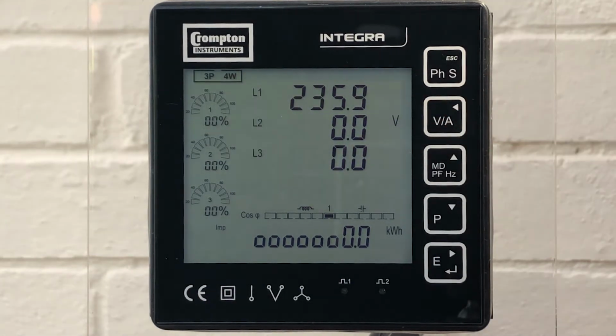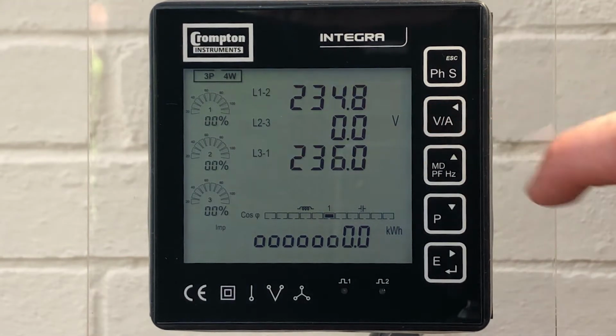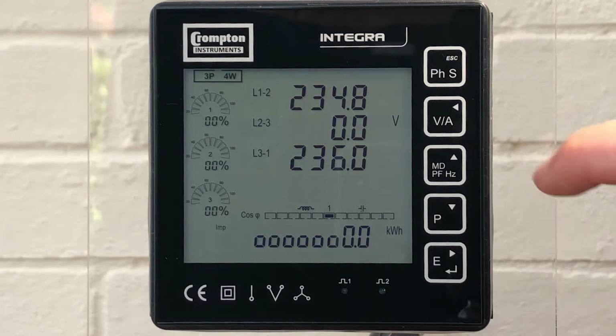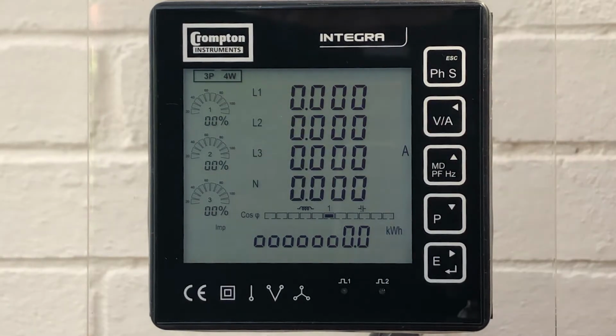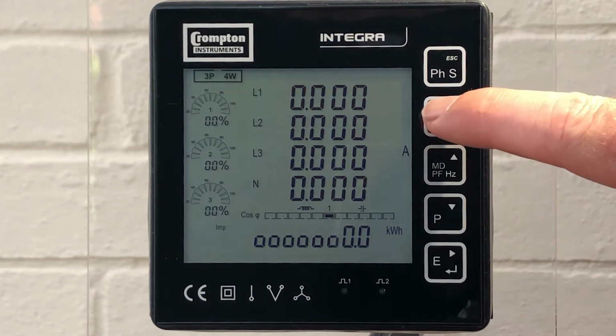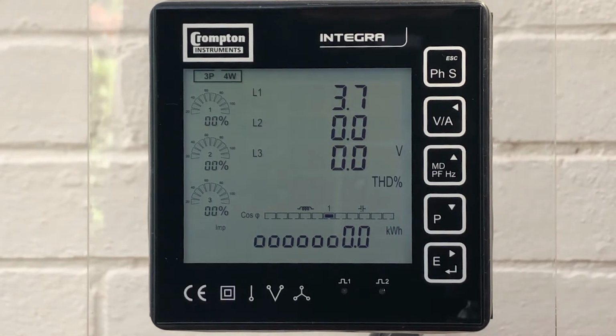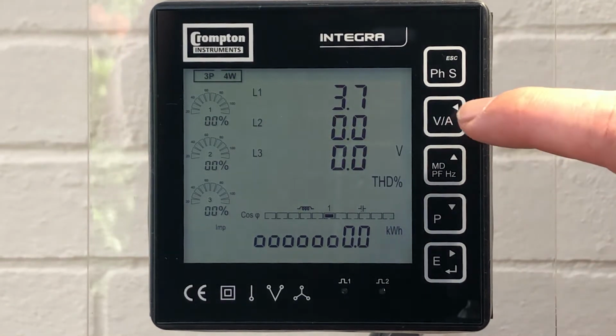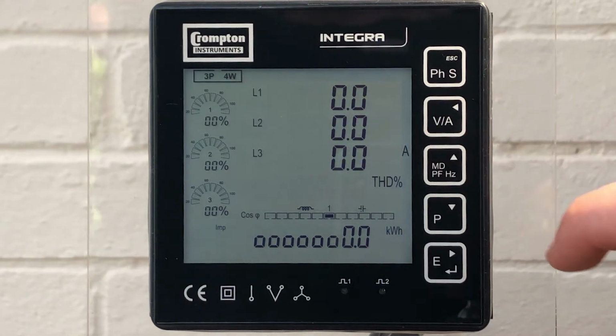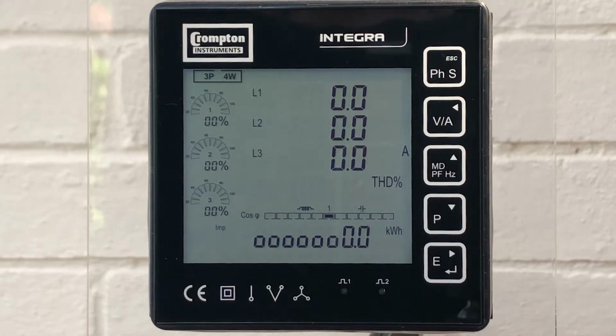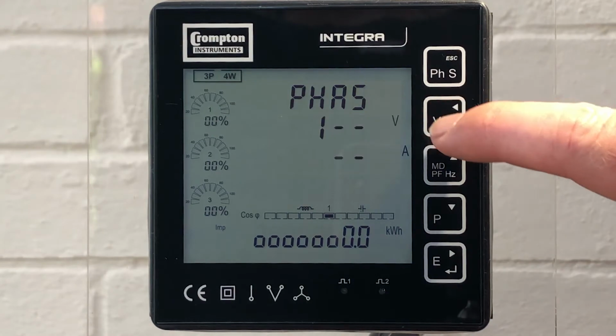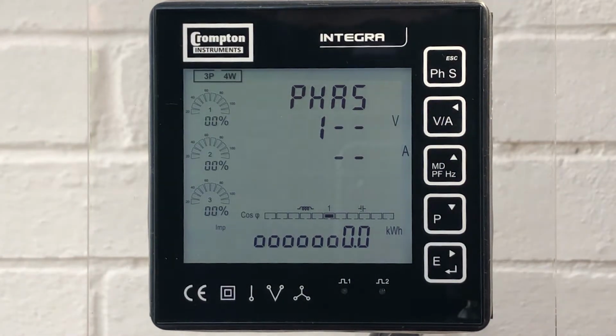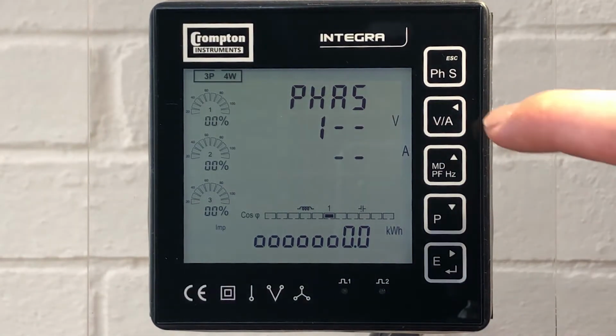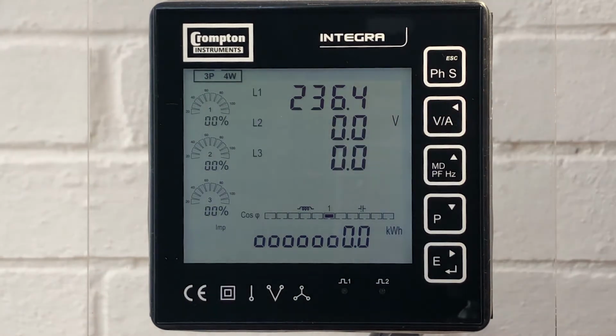Now if we press the VA button, it's going to show phase 1, 2 and 3 voltage, line to neutral and line to line, the current on all phases and neutral, and the total harmonic distortion of the voltage on all phases, and the total harmonic distortion of the current on all phases in a percentage. This screen shows the phase sequence of the voltage and the current.